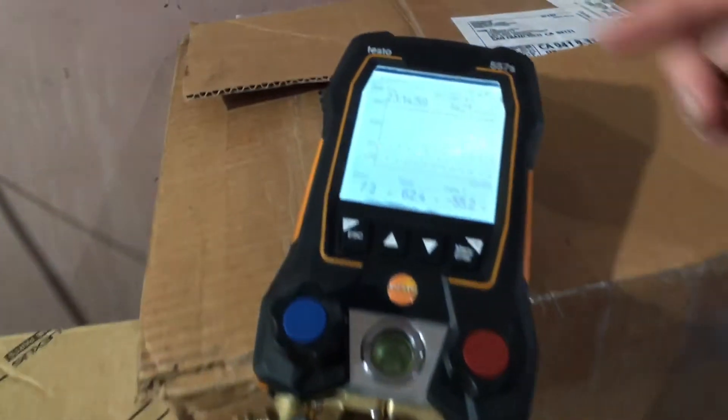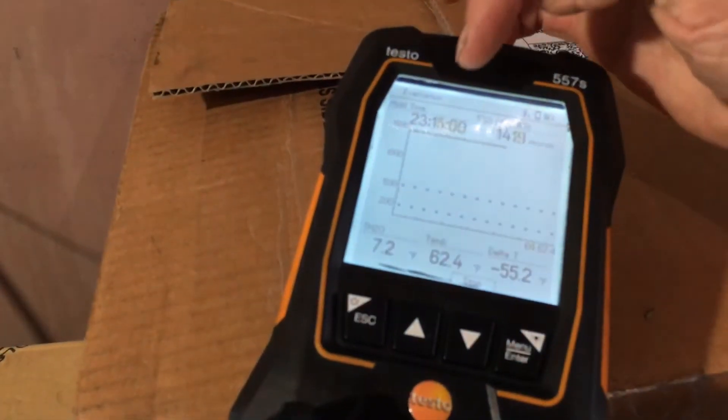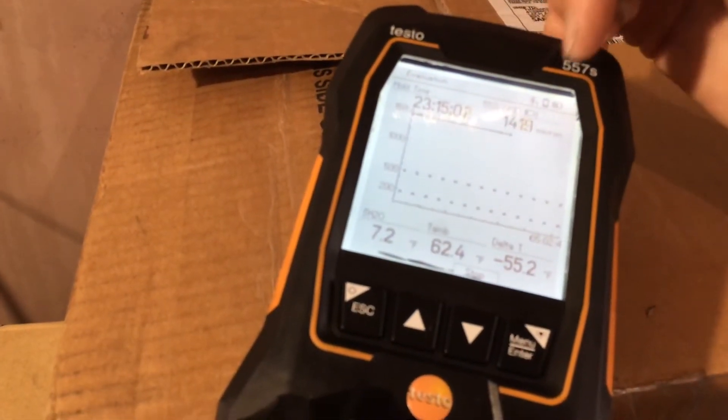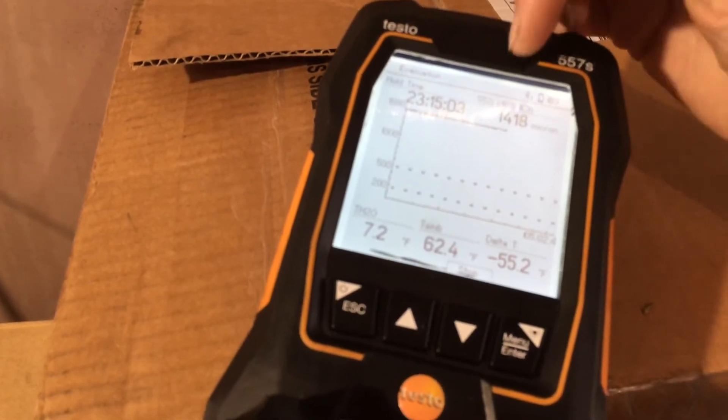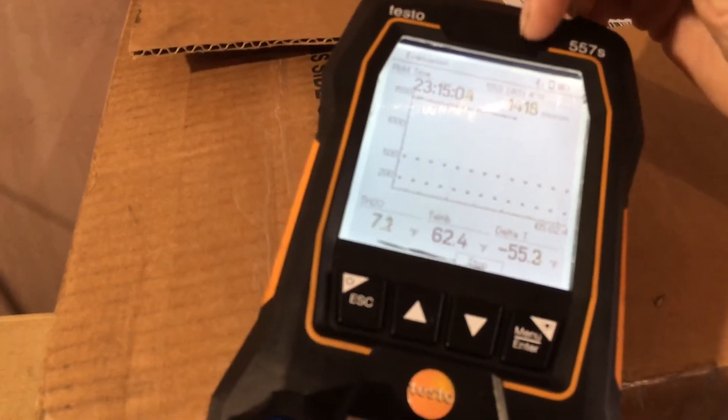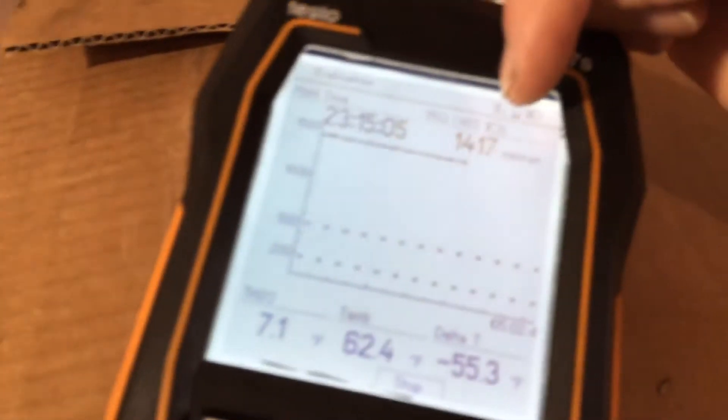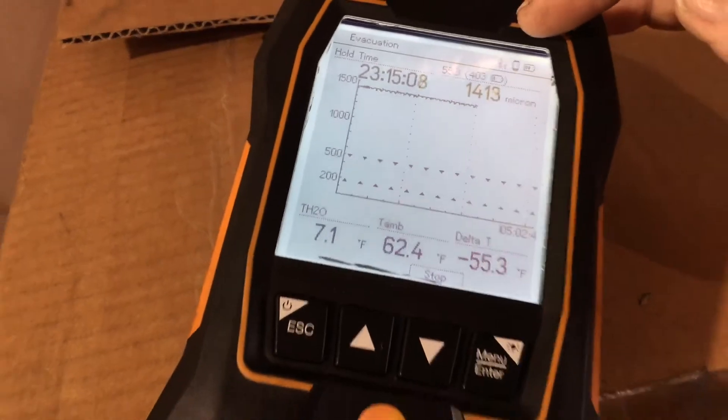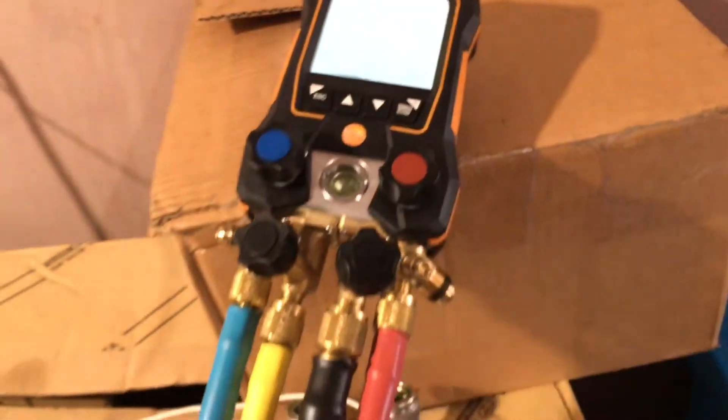11:23 AM, almost 12 noon. So since just a little after midnight until 12 noon the next day, our vacuum has risen to 1400 microns.